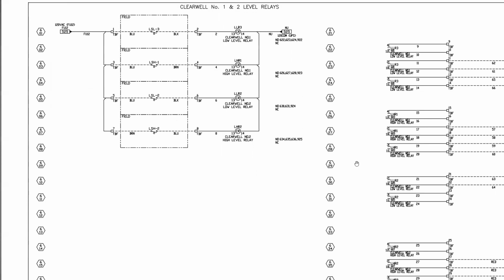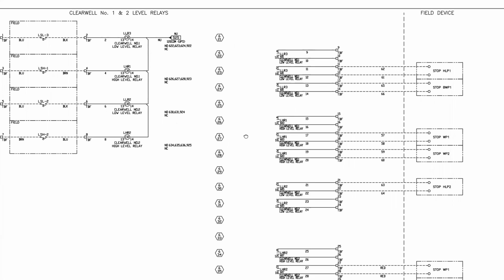So if we go to 622, which is this page, and it's right here, it's wired to literally nothing. Fantastic. We go here, 623 is wired to stop high lift pump. 624 is wired to stop backwash pump. So these floats are wired to positions to stop the HLP, which in this case is a high lift pump, BWP, which I believe is a backwash pump or break water pump.